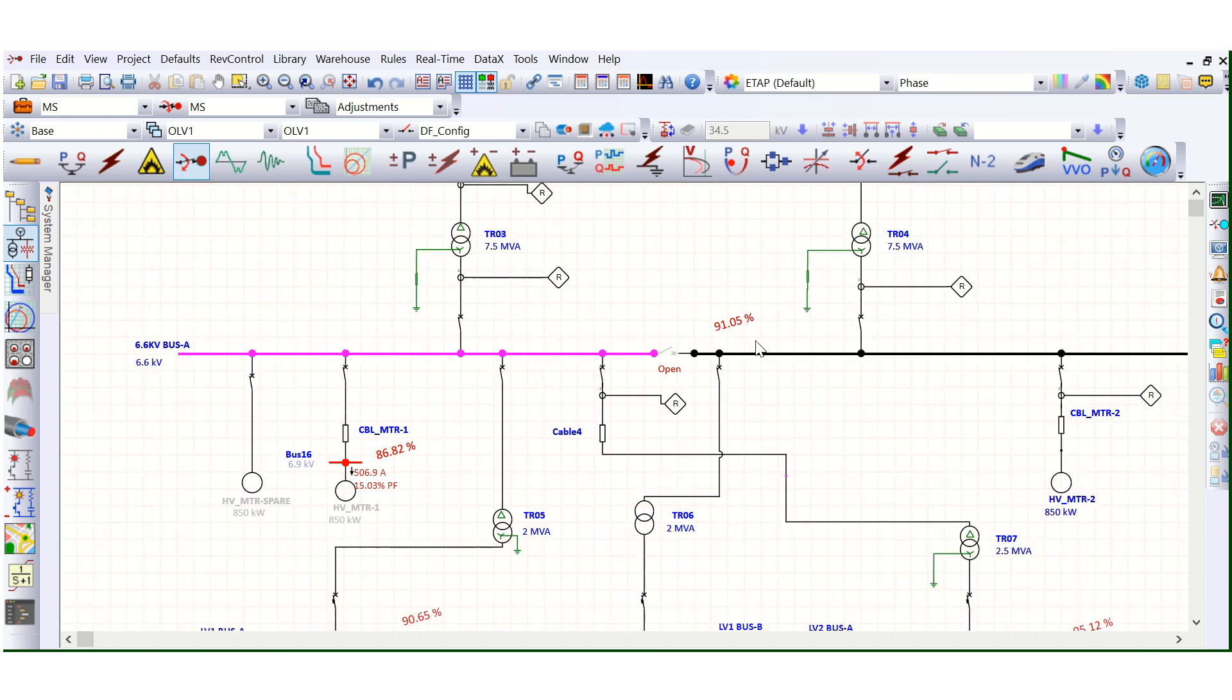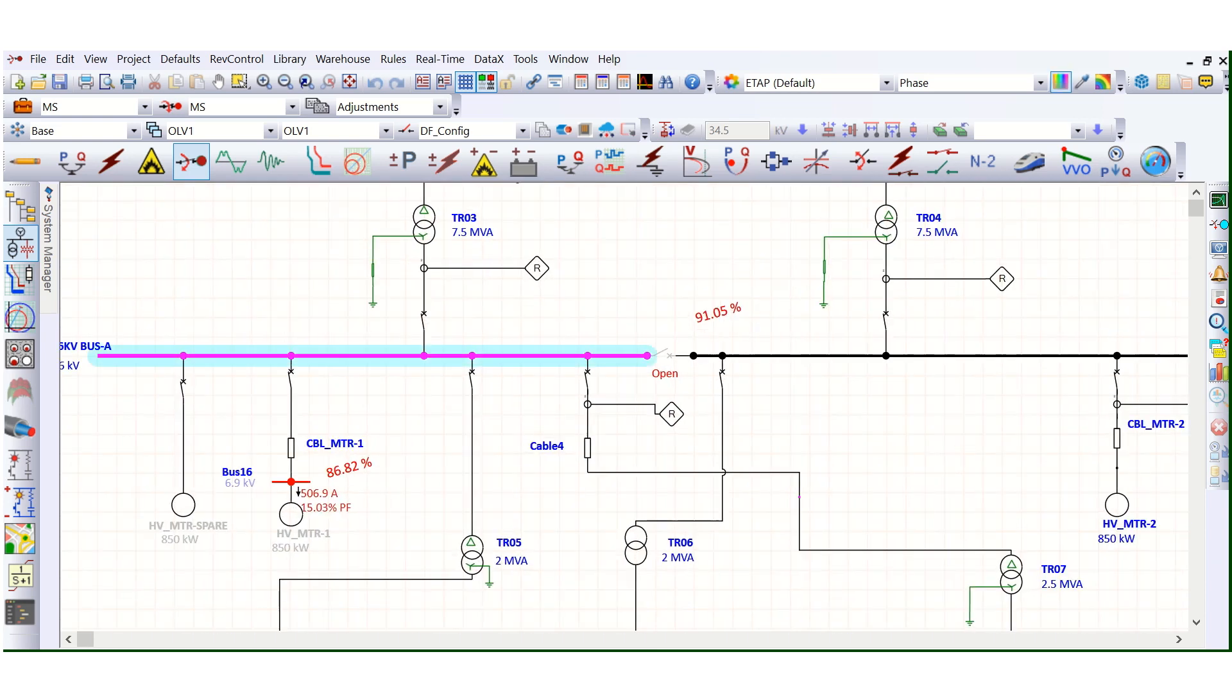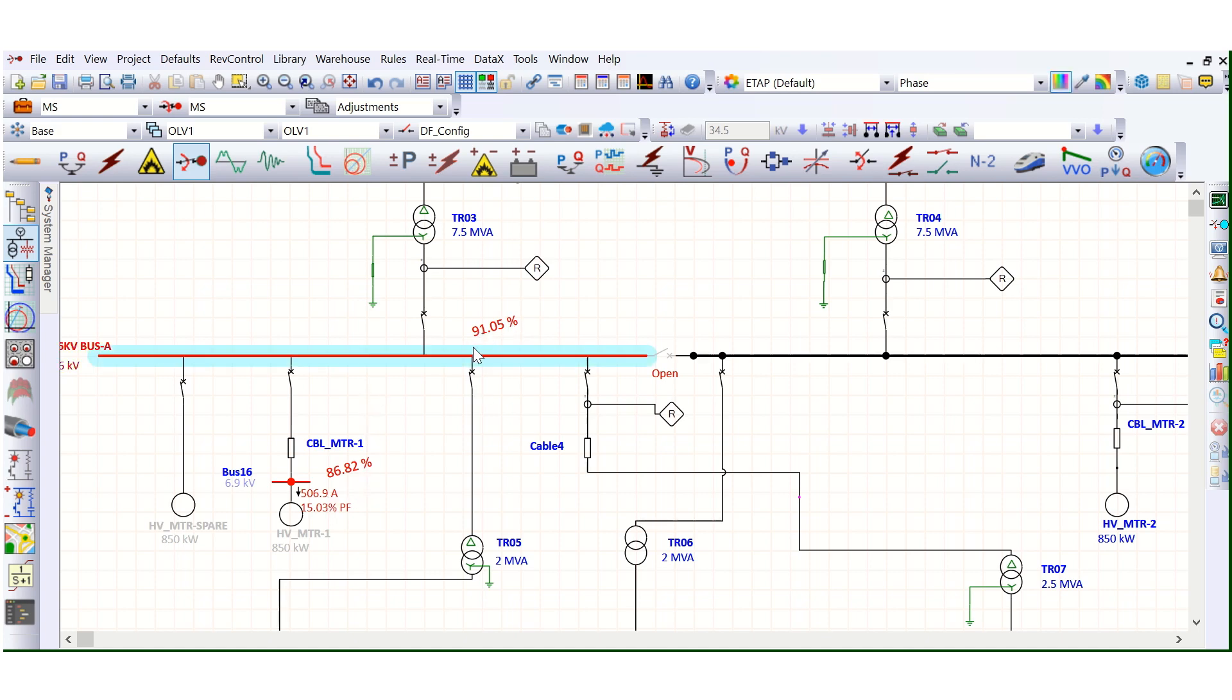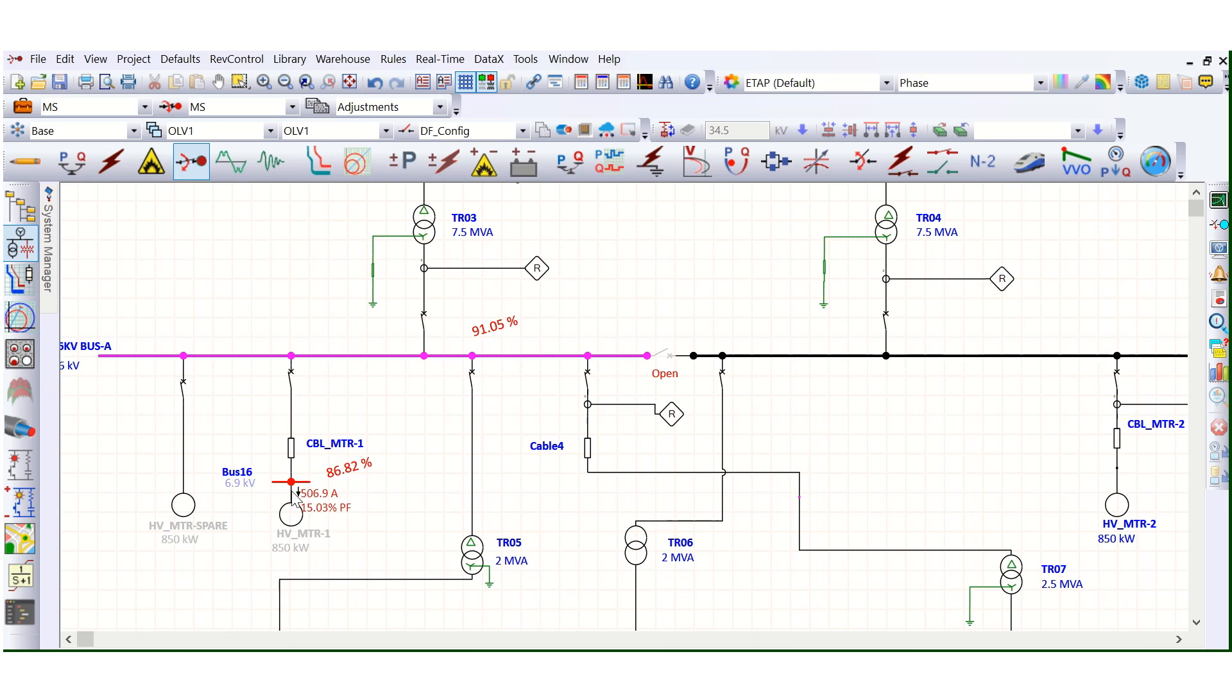So it's fine. It's fine now. There is no issue. And this is the bus voltage 91.05%. So bus voltage, motor terminal voltage. Generally this motor terminal voltage, this motor terminal voltage, this limit is 85%. And here, here the bus voltage is 91%. So it is more than that. More than the limit. So this is fine.